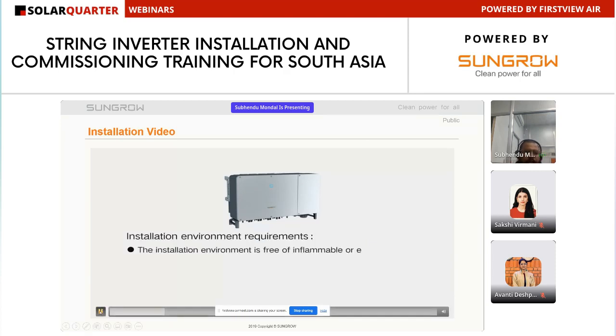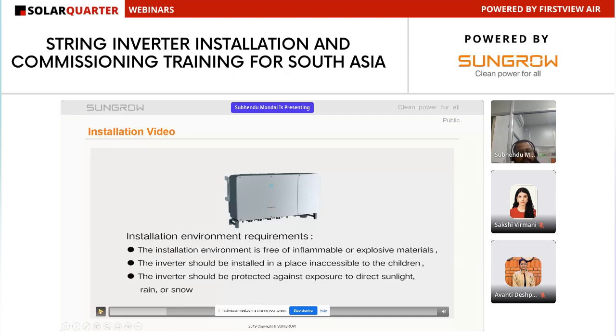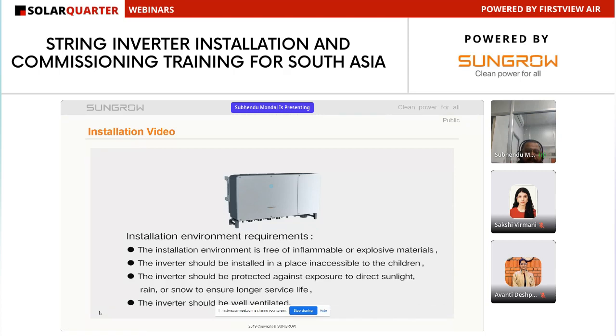As I have already discussed, our inverter is IP66 protected, so we can install it inside or outside, in outdoor also. The installation environment should be free of inflammable or explosive material. Our inverter should be installed in a place inaccessible to children. The inverter should be protected against exposure to direct sunlight, rain or snow, and it should be well ventilated. It should be installed in a proper place so that we can do maintenance activity in future.